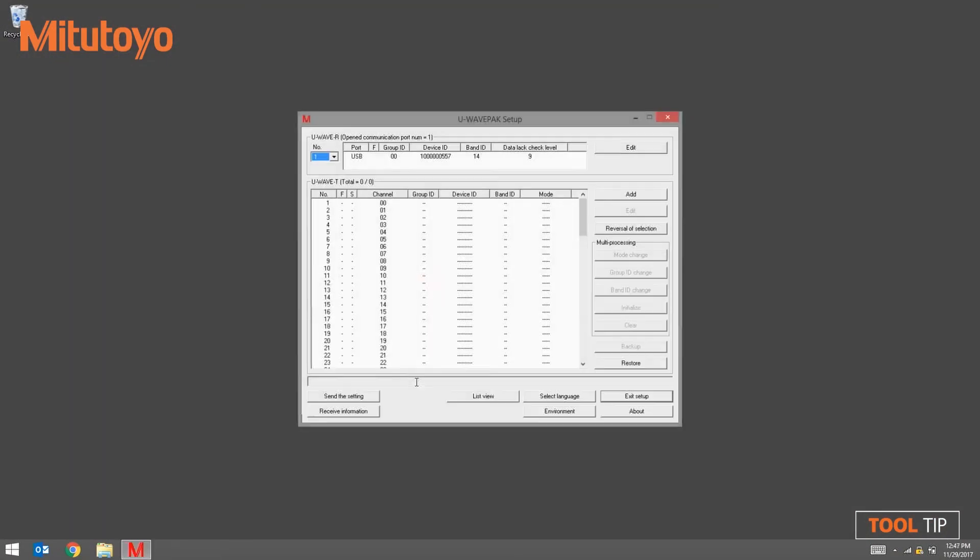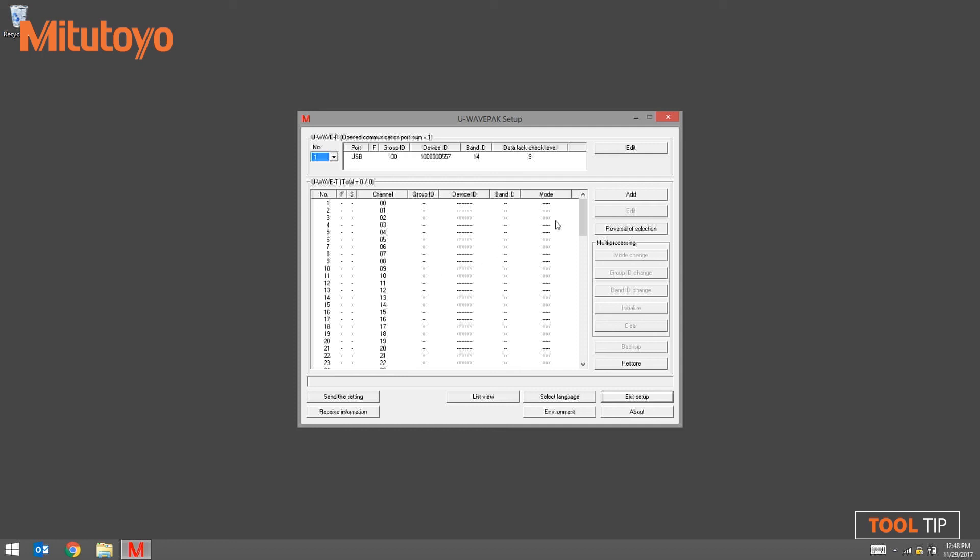Next we're going to launch the U-WAVEPAK software. Press Setup Start to begin pairing the transmitter to the receiver. The setup screen is divided into two sections. The top section represents the receiver that is currently plugged in, and the bottom section represents the transmitters that are currently paired to the receiver. To begin adding a transmitter, click the Add button at the upper right-hand corner of the window.